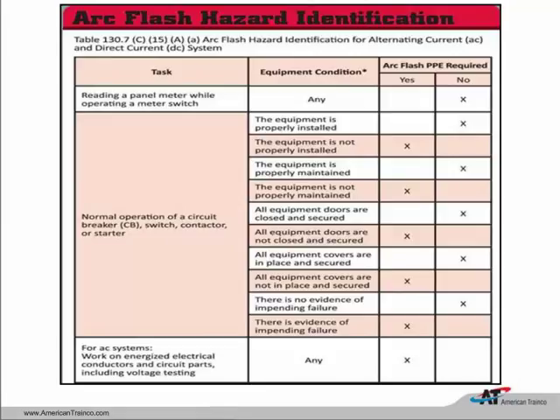And so when we revised this chart, you can see the equipment is not properly maintained. If the answer to that is yes, then we are going to have to wear some arc flash PPE. So if you believe your equipment has been properly maintained, hopefully you have that documented in accordance with the manufacturer's instructions. Otherwise, we're going to be putting on some arc flash PPE.